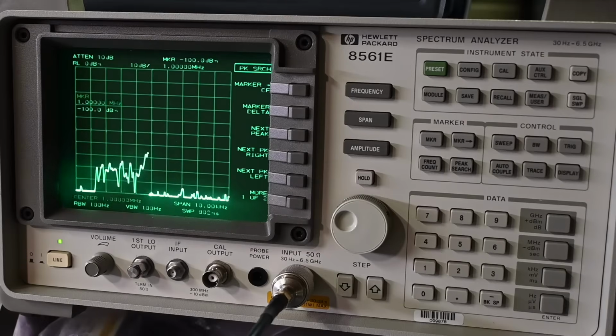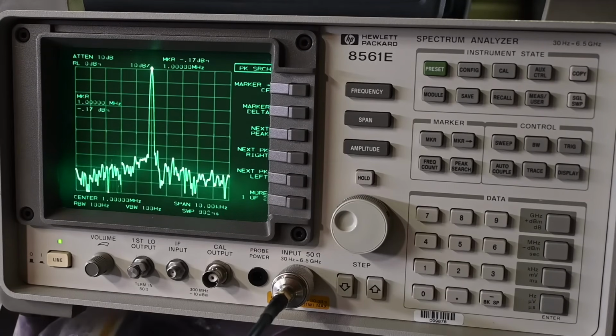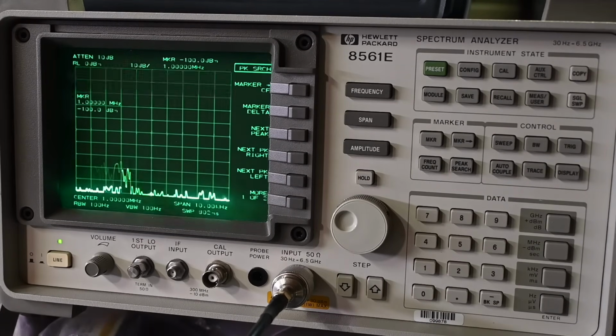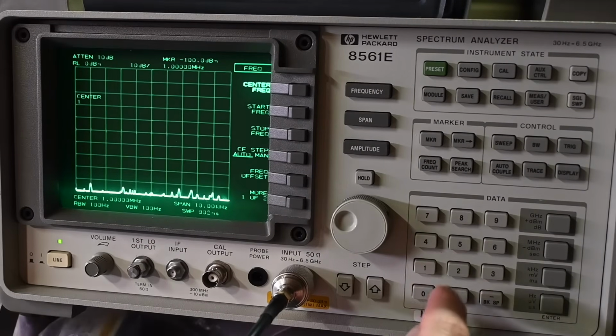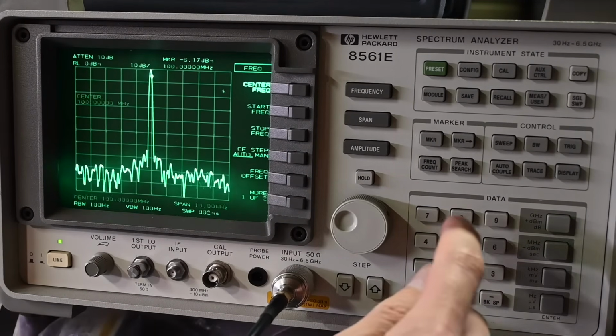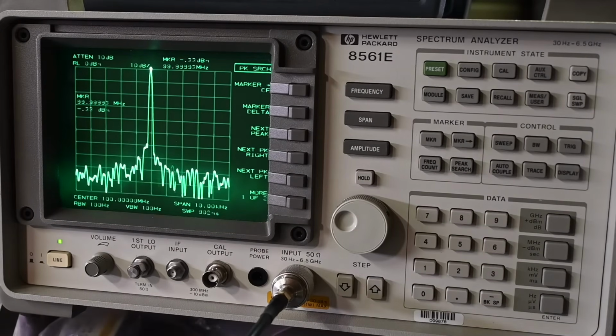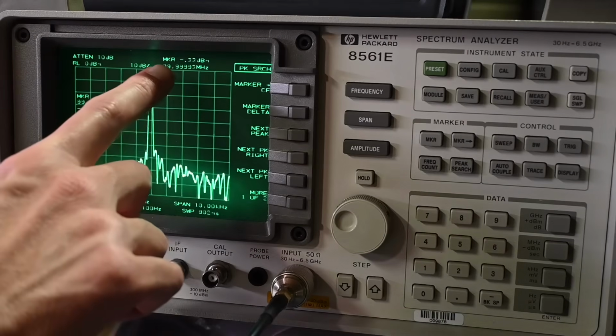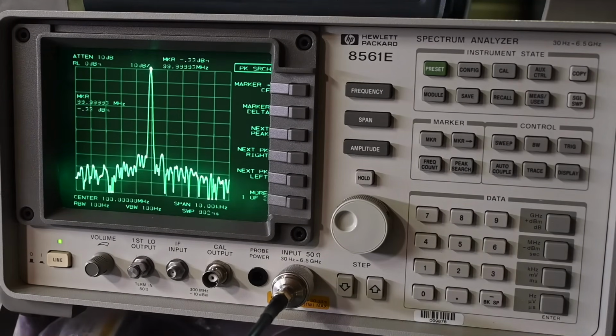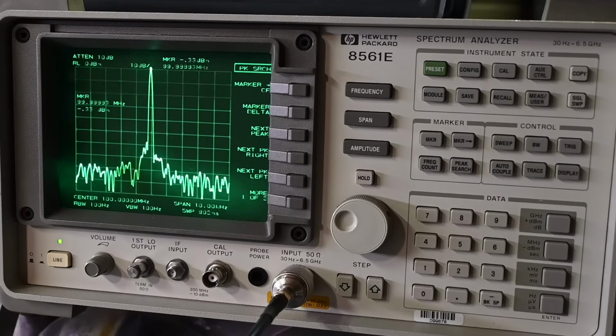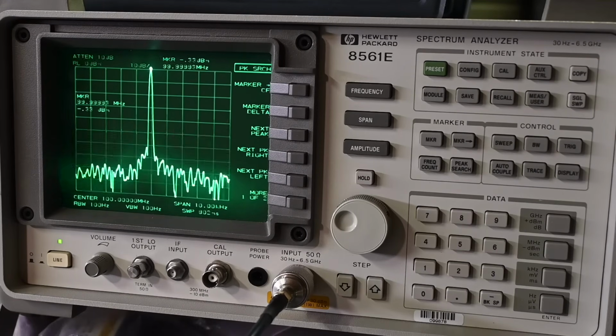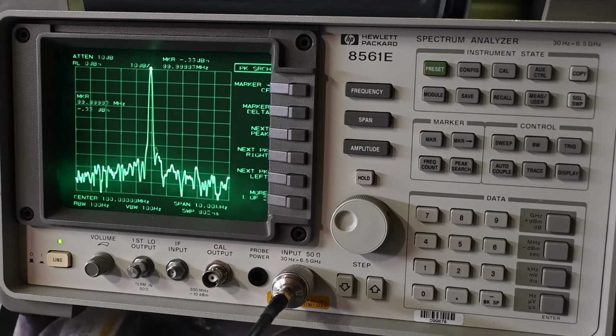0 dBm. So let's change this. Let's go to, say, 100 megahertz. So go frequency 100 megahertz. So let's go over here, frequency, center frequency 100 megahertz. Okay, so again, the amplitude looks fine. Frequency is pretty close right there. It's not exactly on 100 megahertz, but very, very close. Now again, with this signal generator, it should be sitting spot on the frequency, and I'll connect it to the frequency counter. We'll take a closer look at the actual output frequency, but this looks very, very close here, and could be a slight inaccuracy in the spectrum analyzer, although it's quite accurate. It's been calibrated, but nonetheless, it is sitting quite close there, so I don't see any major problems.